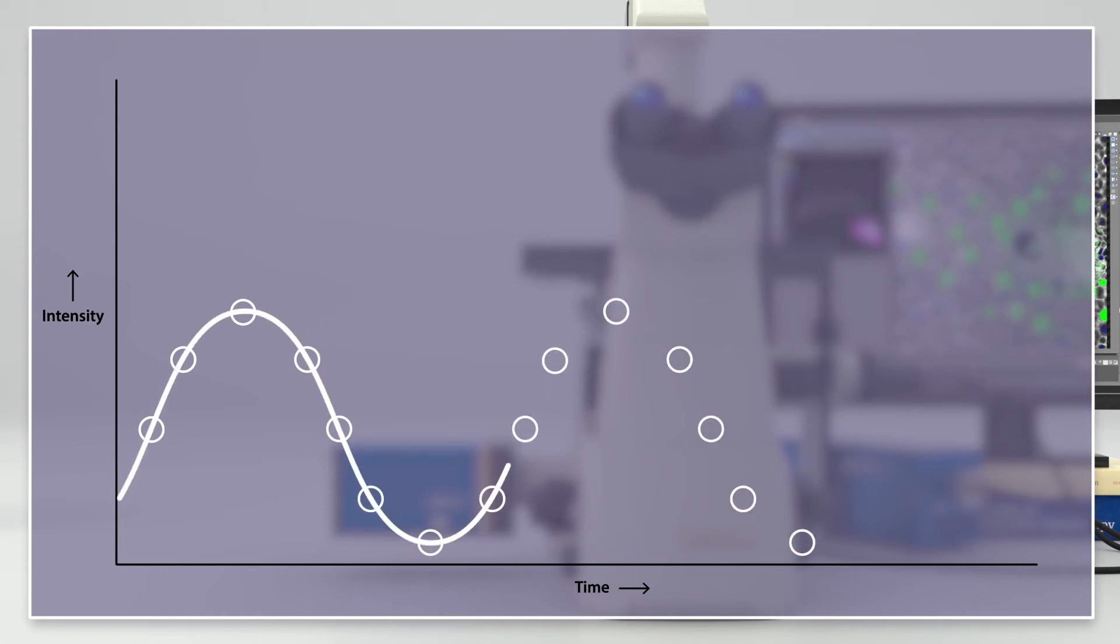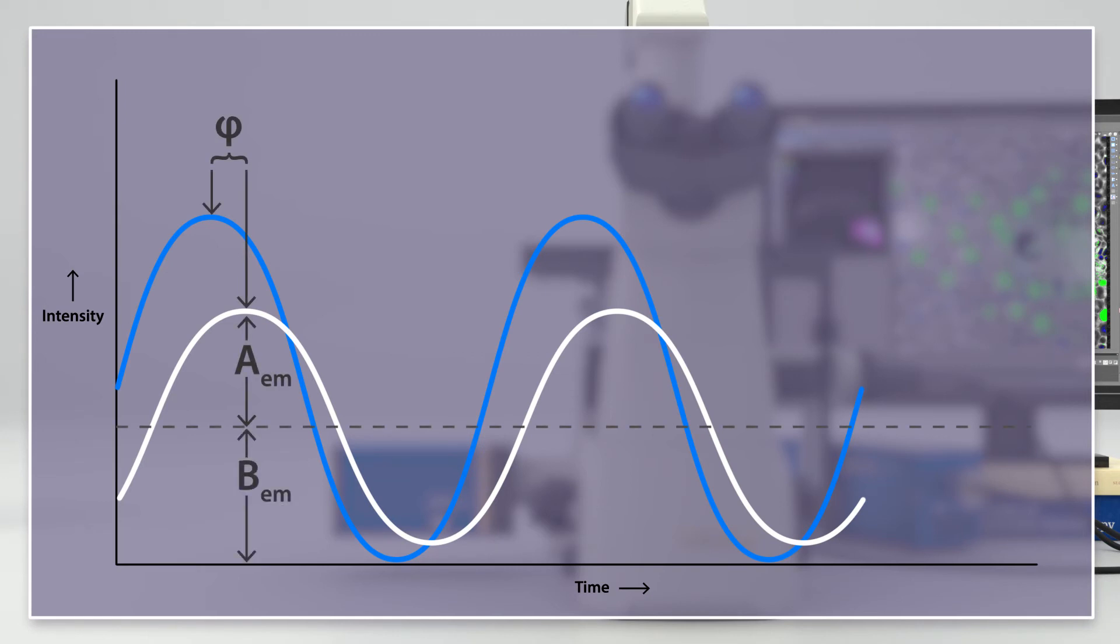Finally, a sine curve is fitted into the measured values in the images I1 to I4 for each pixel. This sine curve provides the phase angle phi, the amplitude A-emission, and the constant component B-emission, which are used to determine the corresponding fluorescence lifetime values.